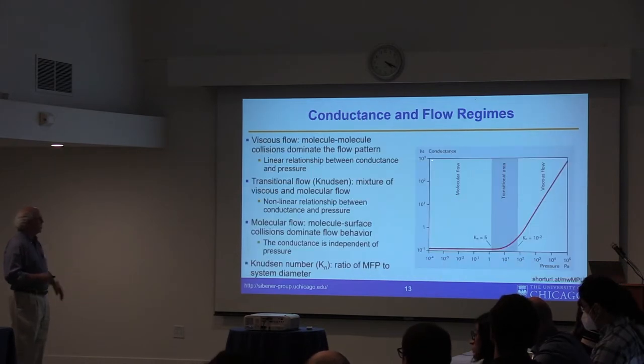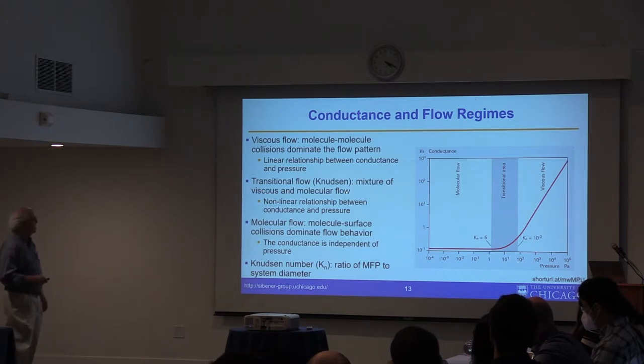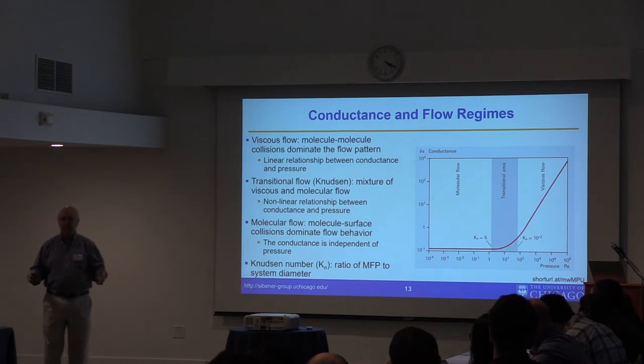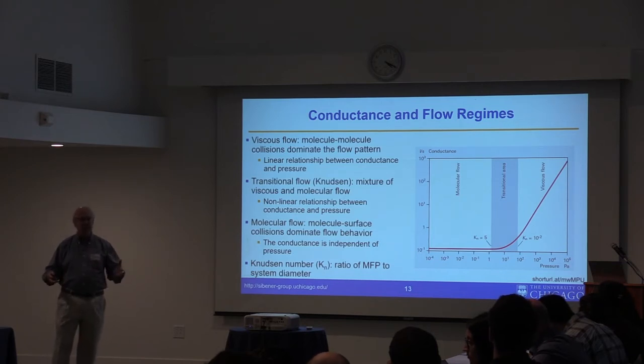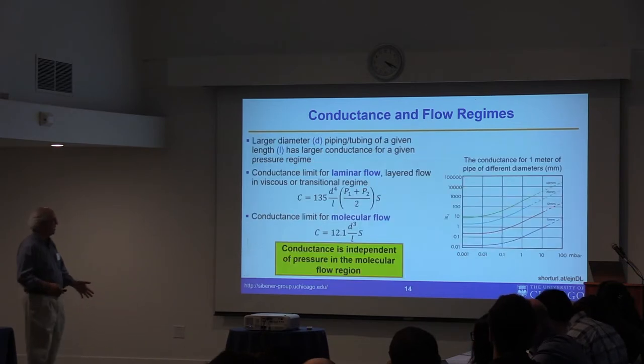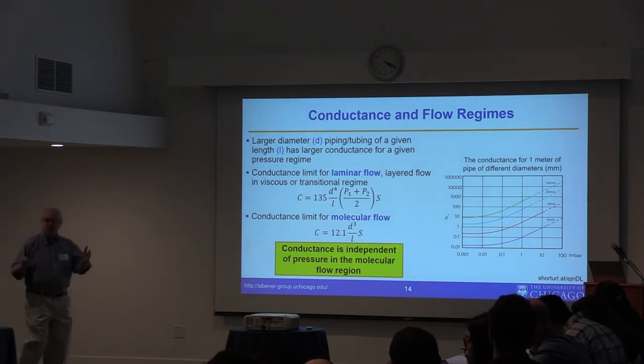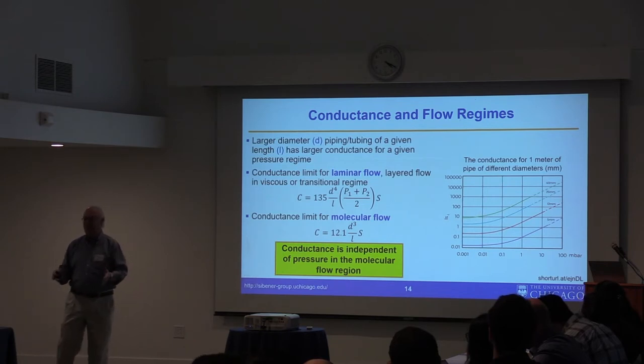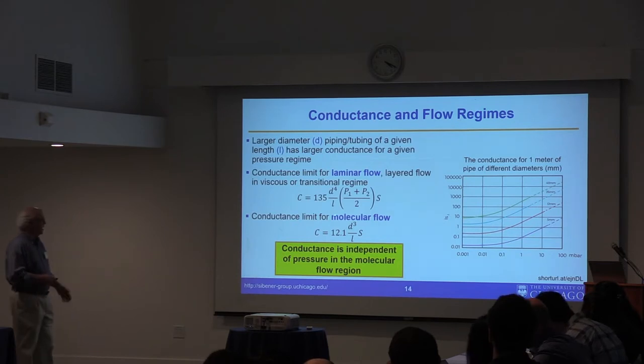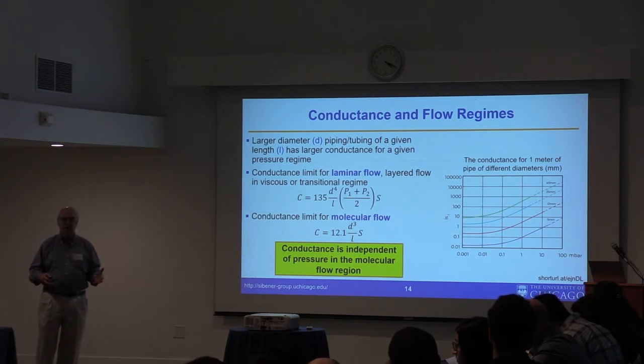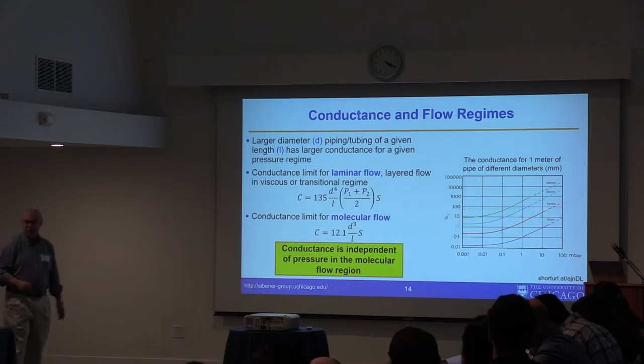You have different flow regimes characterized by Knudsen numbers, and molecular flow can dominate in different ways. It's connected with the mean free path. Sizing the plumbing with the pumps and with the experiment is a system — mess up one part and the whole system suffers. In the laminar flow regime, conductance scales as the fourth power of diameter. In the molecular flow regime it drops to D cubed, so there's a different scaling for particle flow through confined tubing. If you're building a machine the size of a room, you really want to get this right.